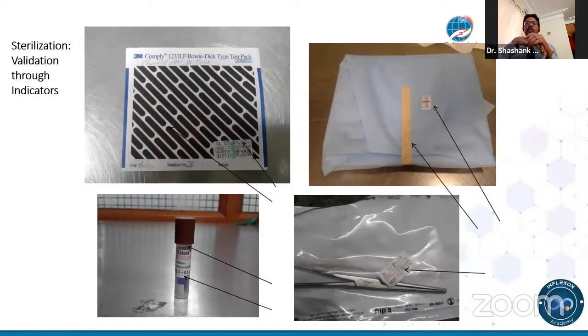Yeah, so I think this is something that has already been talked about. The sterilization validation involves an external class 1 indicator on your packaging materials, and an internal class 4 or class 5 indicator inside the packaging, which ensures that the sterilant has penetrated inside the packaging, and the load is monitored by a biological indicator. Very important that it should be for every load.